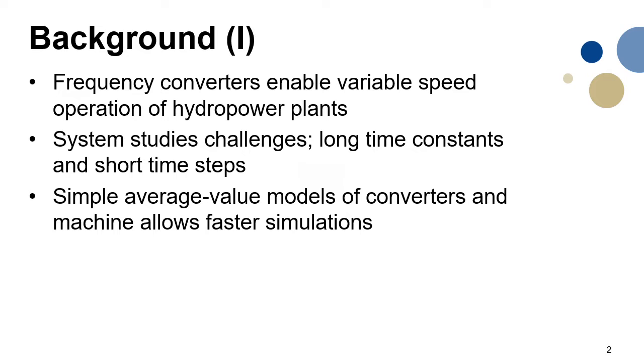The modeling of variable speed hydropower plants can be problematic, however, because of the differences between the dynamics of the hydraulic and electrical system, where the hydraulic system is characterized by long time constants and needs time simulations over a long time period, whereas the frequency converters with high switching frequencies need to be simulated with short time steps. As a result, the simulations of variable speed hydropower systems might become excessively computational expensive and time consuming, therefore leading to reduced size and complexity of the modeled systems.